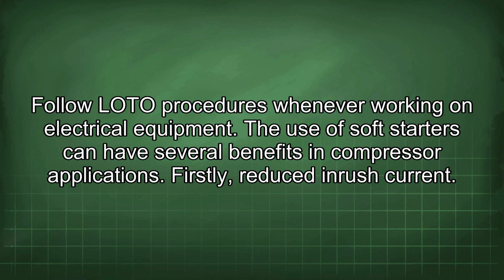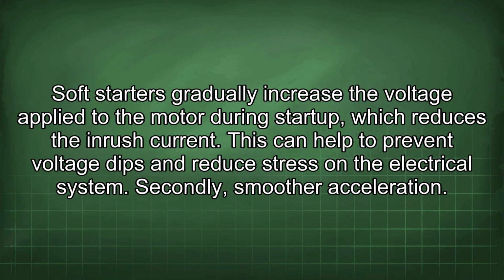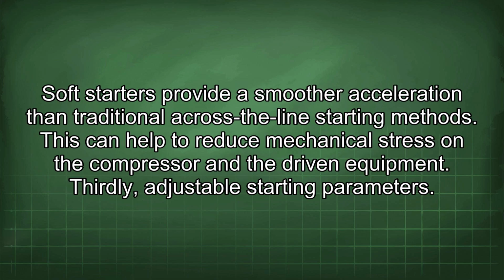The use of soft starters can have several benefits in compressor applications. Firstly, reduced inrush current. Soft starters gradually increase the voltage applied to the motor during startup, which reduces the inrush current. This can help to prevent voltage dips and reduce stress on the electrical system. Secondly, smoother acceleration. Soft starters provide a smoother acceleration than traditional across-the-line starting methods. This can help to reduce mechanical stress on the compressor and the driven equipment.